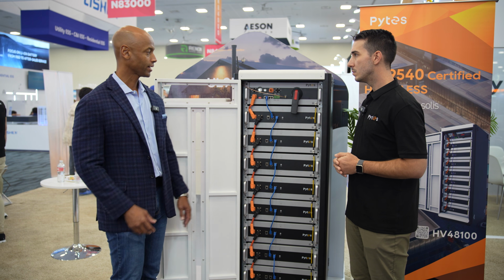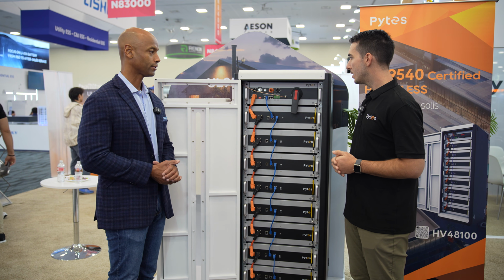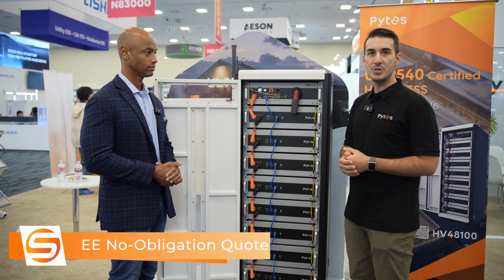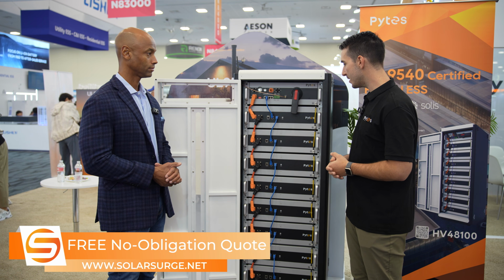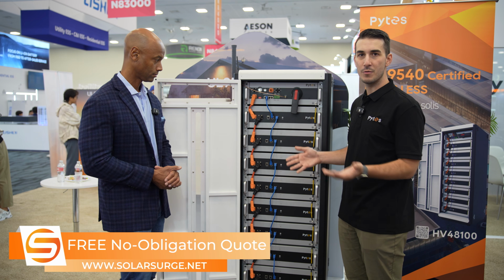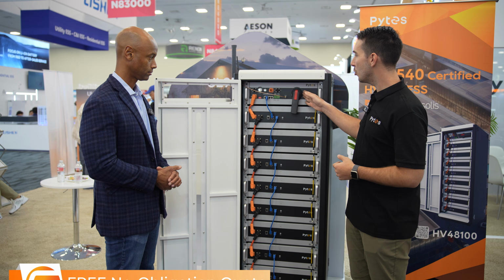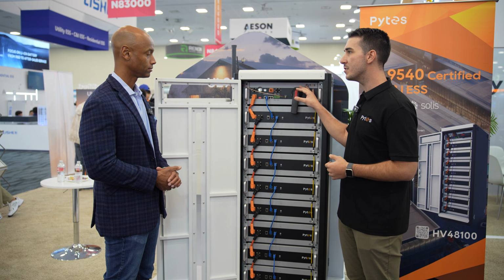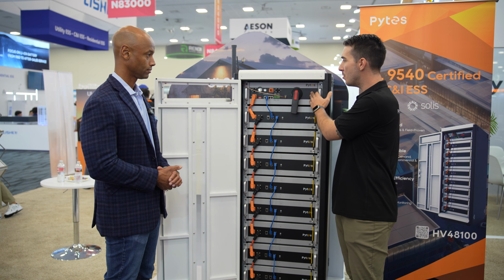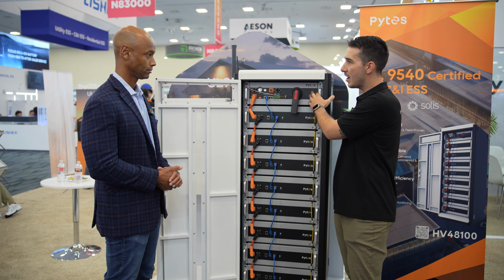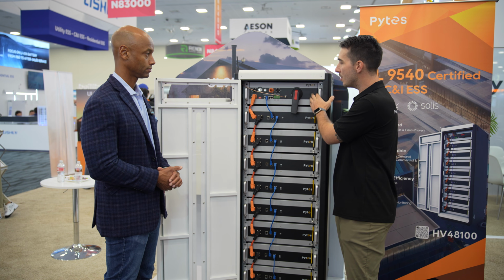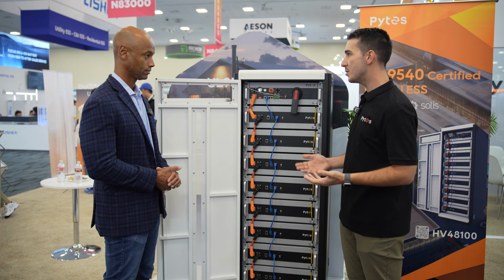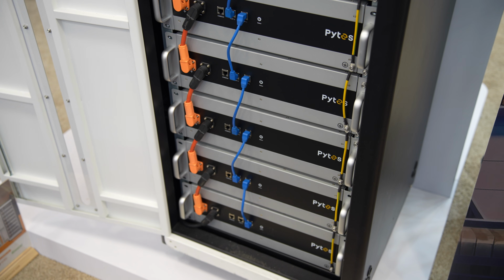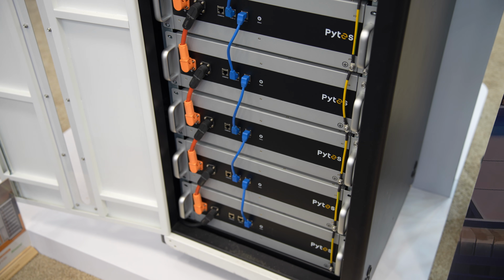Logan, anything else the audience should know about the high voltage solution? Maybe just a quick rundown of the architecture. It looks really similar to our V5, we're just doing series connections, not parallel. The top unit is our battery control unit, the brains of the entire system, the one running the show. This is what the installer interacts with, and what's communicating with our inverter. Each battery module still has its own individual BMS, so we've got full protection for each component included in the cabinet.